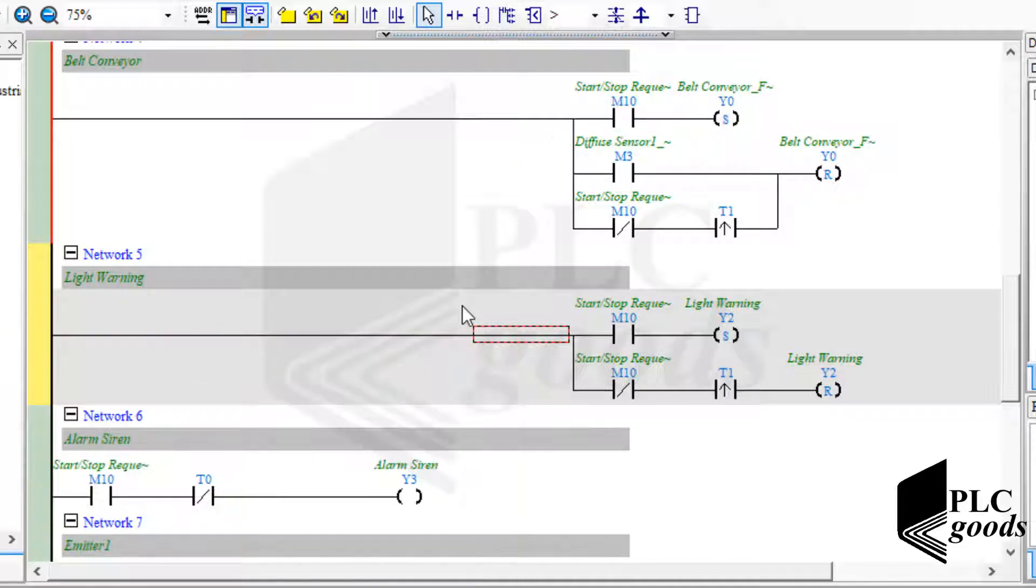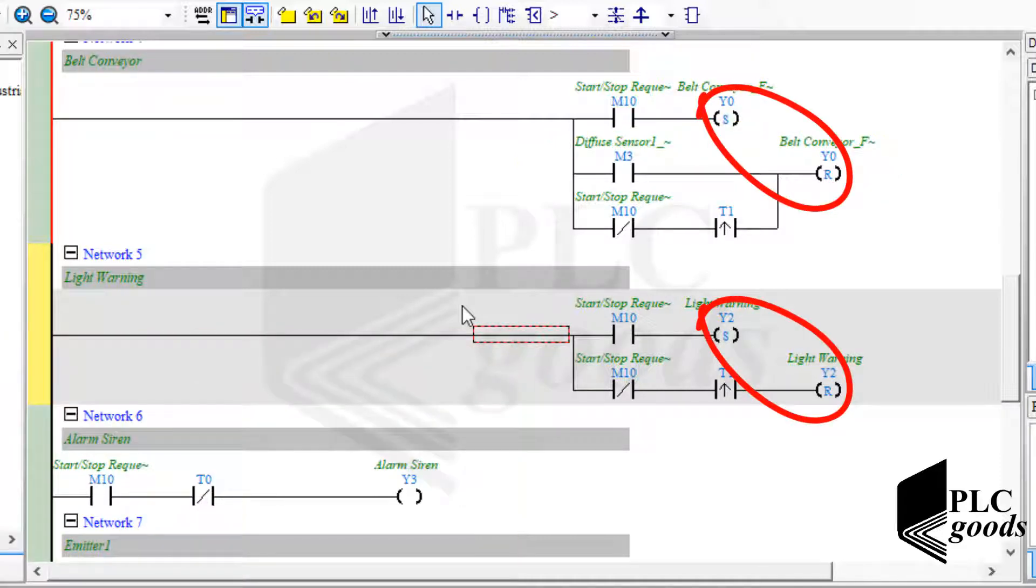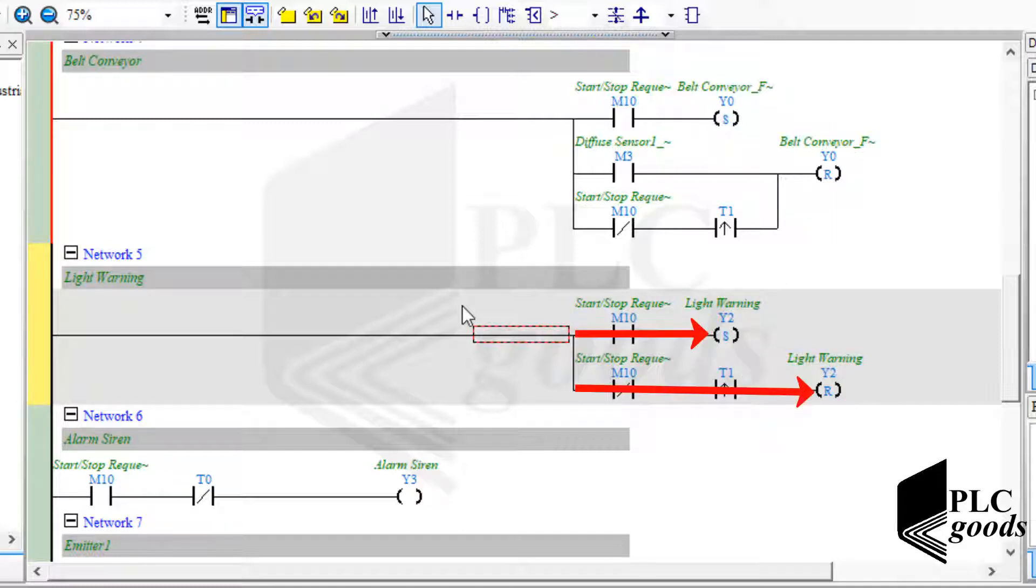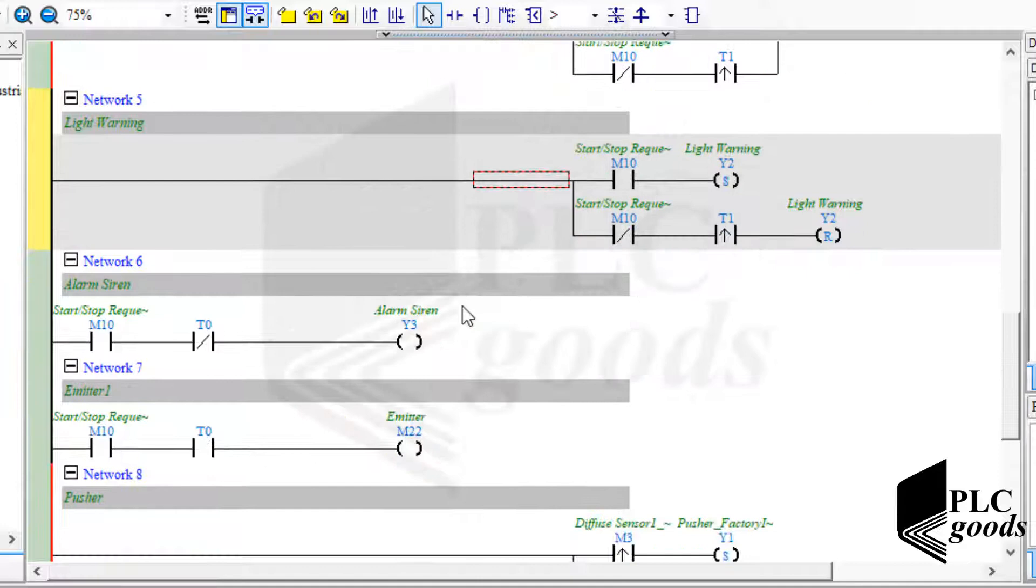As you see, set and reset instructions are used together. If I determine some conditions to set an output, naturally there are some conditions to turn it off. Note that I usually use reset instruction after set, because an electrical device that is off is safer than when it's on. So if both conditions are true to activate set and reset instructions to turn on or off a specific output, PLC will work based on the last instruction.